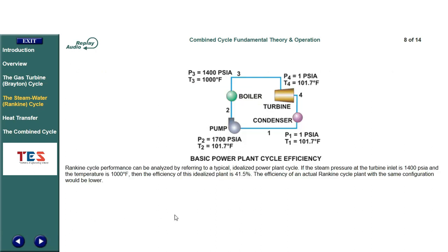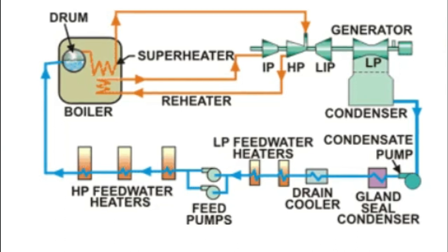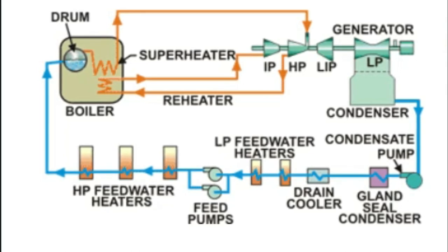Rankine cycle performance can be analyzed by referring to a typical idealized power plant cycle. If the steam pressure at the turbine inlet is 1400 PSIA and the temperature is 1000 degrees Fahrenheit, then the efficiency of this idealized plant is 41.5%. The efficiency of an actual Rankine cycle plant with the same configuration would be lower. Actual Rankine cycle plants are considerably more complex than the basic cycle.